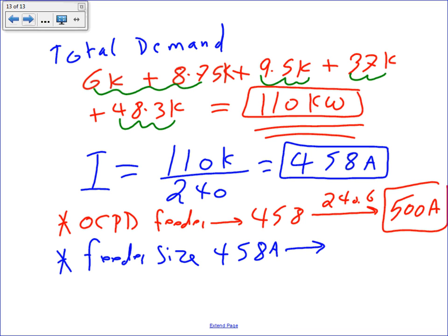Can you guys give me, based on 310.15(B)(16)? Now, this is where 75 becomes a big deal. 75 degree column. What do we get? One conductor. I know it's big. 700. 700. Thank you. 3 conductors, 700 kcmil. Now, some of you would say, Chad, what happened to the derating of the neutral? I'm taking a full neutral, because I don't want to complicate things. But we can derate the neutral. We can cut the neutral by 0.7.